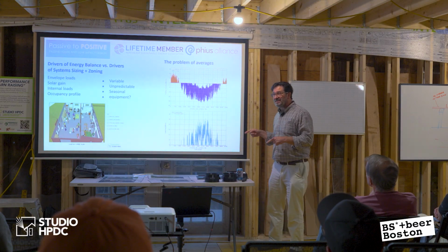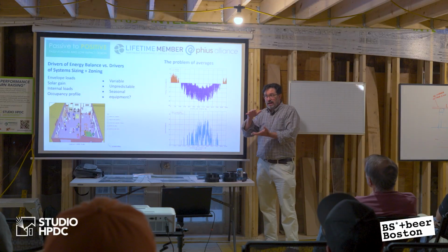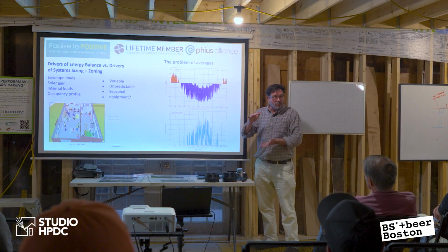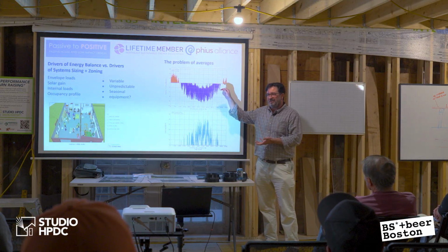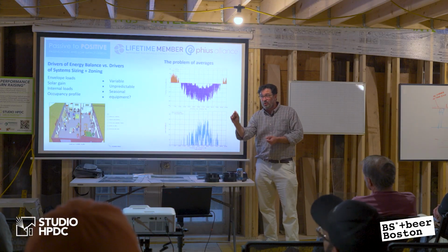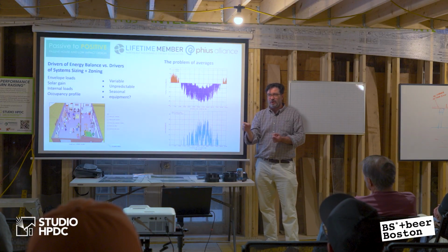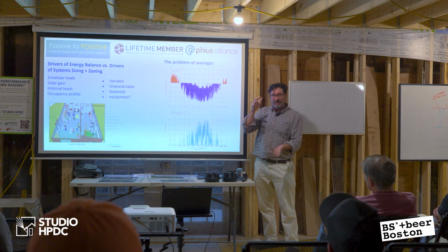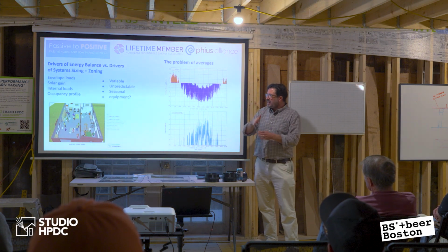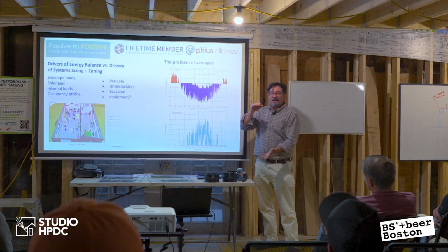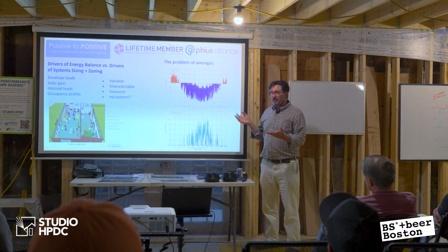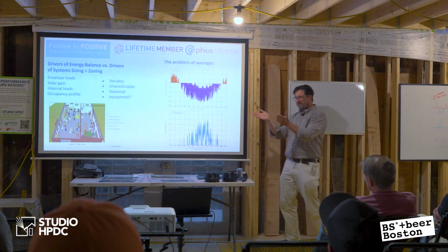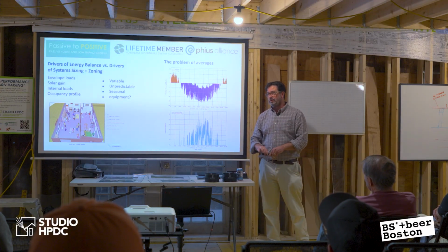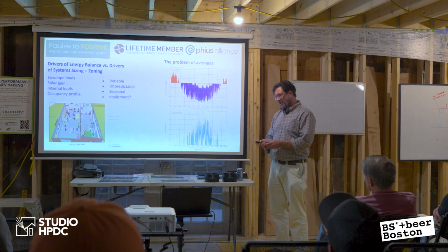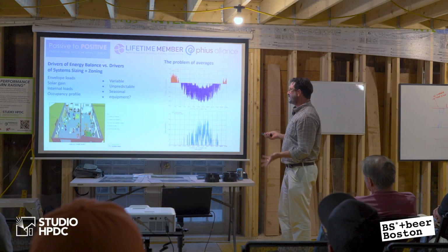So if you're right sizing, if you're really being constrained for right sizing your equipment, but you're not accounting for the latent loads and the sensible heat ratio, which is the amount of sensible heat versus humidity that gets removed. If that sensible ratio has to be higher to be more efficient, then you get less humidity removal. Now we're right sizing our system, as you pointed out. This is an incredible dovetailing. You're right sizing your system for the wrong load. So these are the kinds of things an annoying, somewhat informed client might ask Ross, but he knows the answers.